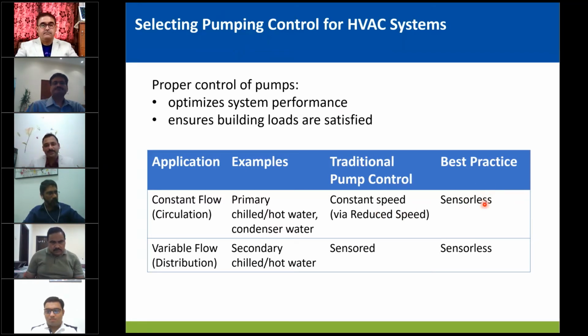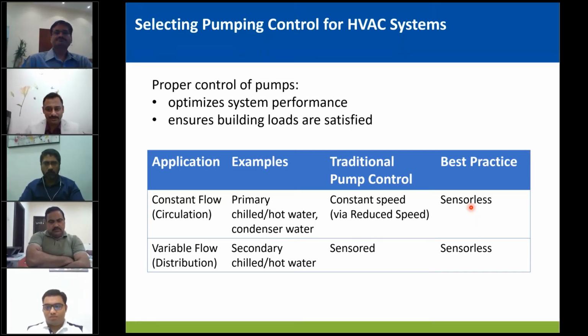When you have a smart pump sensorless control, you could program a flow rate, or you could program a particular pressure, and you could let the pump maintain that particular flow. By doing that, even if somebody adjusts any valves over time or any scaling happens, for example, in a condenser, the flow rate tends to drop when you put it at a certain frequency, because we don't know the flow rate. We are not actually measuring the flow rate on the traditional pump control.